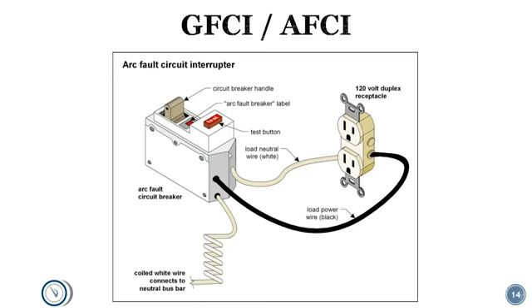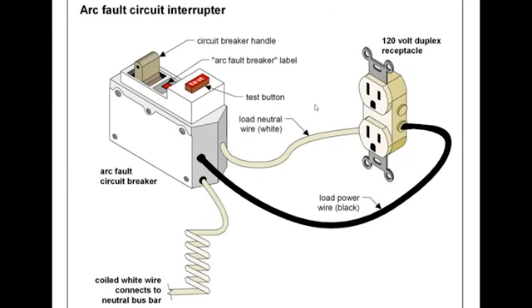And so it's very important whenever you're wiring up anything to make sure that it's properly grounded, properly bonded throughout the structure. But also keep in mind that in some cases, especially with convenience outlets, anything where there's potential moisture involved, a ground fault circuit interrupter, GFCI, is important because, like we mentioned, you could potentially be a ground path and not draw enough amperage to trip a breaker. And so a GFCI basically looks for imbalance between neutral and the hot. Again, this is for 120 volt circuits primarily. Convenience outlets is where you're going to see this more than anything else. But it's important to understand what they do and why they matter.